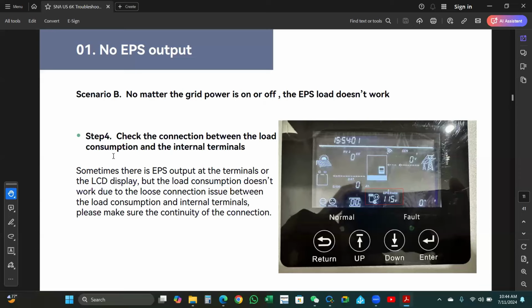Step four. Check the connection between the load consumption and the internal terminal. Sometimes there is an EPS output at the terminal and on the LCD display, but the load consumption doesn't work due to a loose connection between the load consumption and the internal terminals. Please make sure of the continuity of the connection.